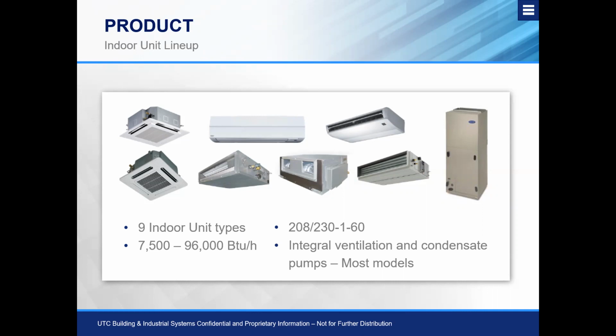Just like we stated before with the Carrier product, most of the models have integral ventilation and condensate lift mechanisms. So the cassette style units have outside air integration and condensate lifts. Low static and medium static have integral ventilation and condensate lifts. High static, of course, has integral ventilation, but does not come with a condensate lift. Neither do the high wall, vertical air handler, or under ceiling units have the ability to have a condensate lift, and only the vertical air handler has outside air handling. And as we stated in the previous product offering, the outside air must be pre-treated prior to entering; it cannot be raw, untreated outside air.